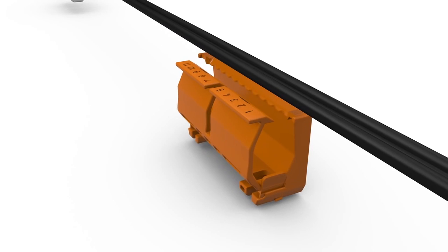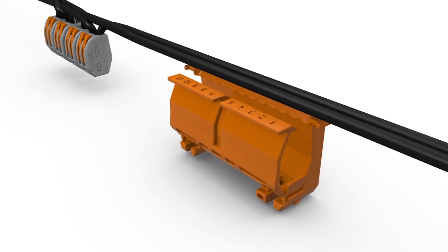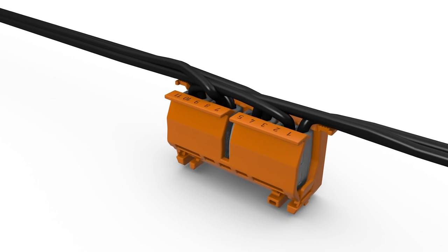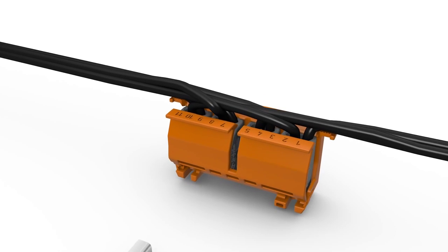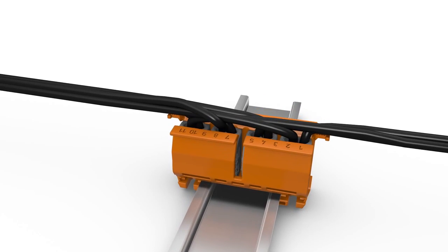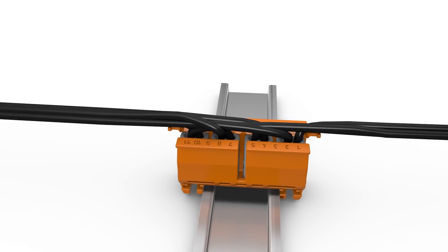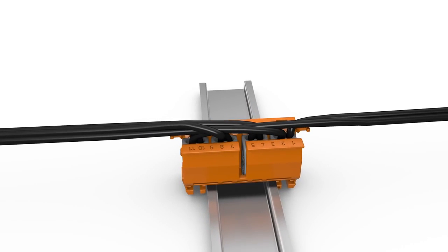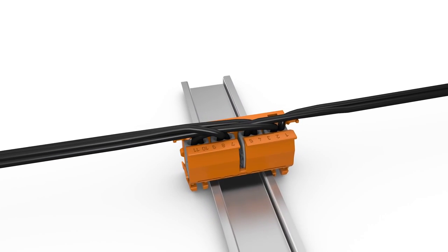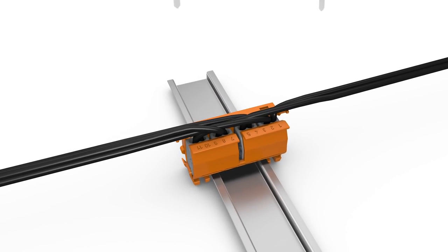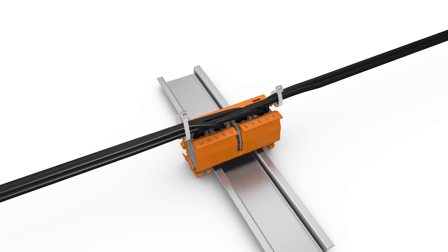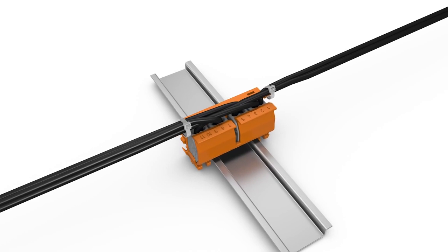In addition to standard applications and building installations, WAGO connectors can also be secured in place for use with mounting carriers, for instance, in distribution boxes. When used with mounting carriers on a carrier rail, cable strain relief can be implemented by adding cable ties at the mounting carrier perpendicular to the terminal block direction.